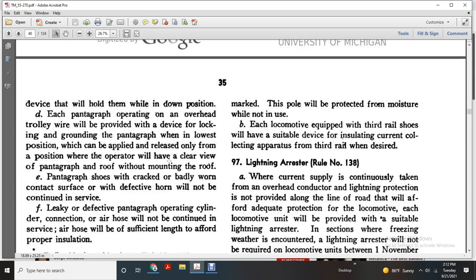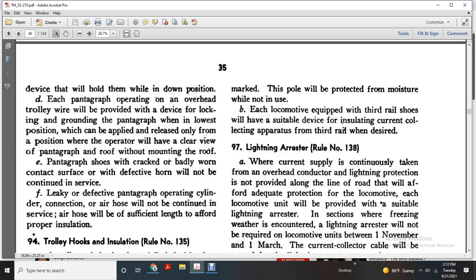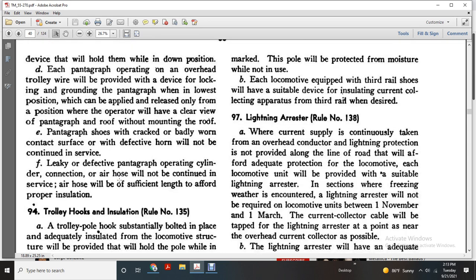shoe with a crack or badly worn contact, shoe with a defect or worn, will not be continued in service. Shoe with a leaky defect in the pantograph operating cylinder connection or air hose will not be continued. Ensure the air hose has additional length for the forward, with proper insulation.